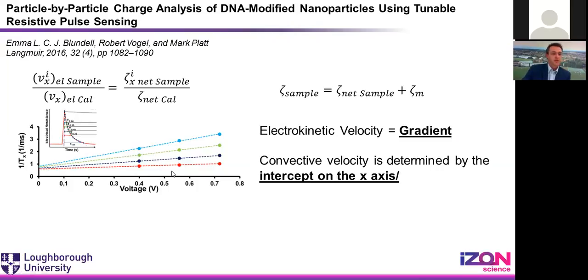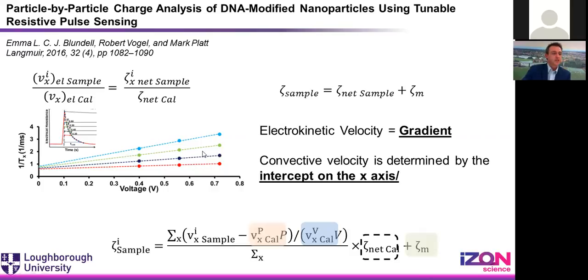And in generating our calibration plot here, what we've been able to do is have a relationship that says the electrokinetic velocity of the particle is proportional to the gradient of the graph that we've generated, and the convection velocity, that is the fluid flow from the pressure head from the top to the bottom cell, is now going to be the intercept on the y-axis. So I take those two equations at the top, and it's a rearrangement, and this is perhaps an equation that you don't necessarily need to put to memory. The software and the formula will produce these numbers anyway, but it will tell you at least where they come from.